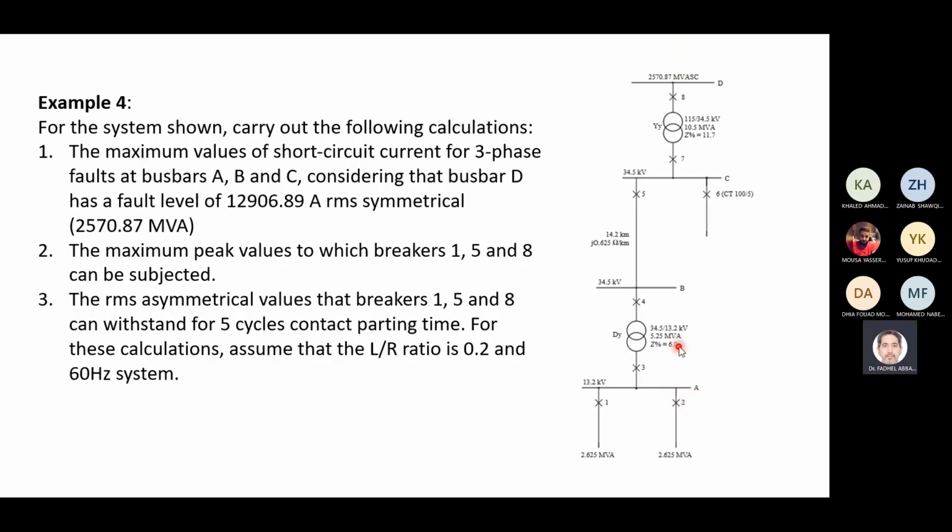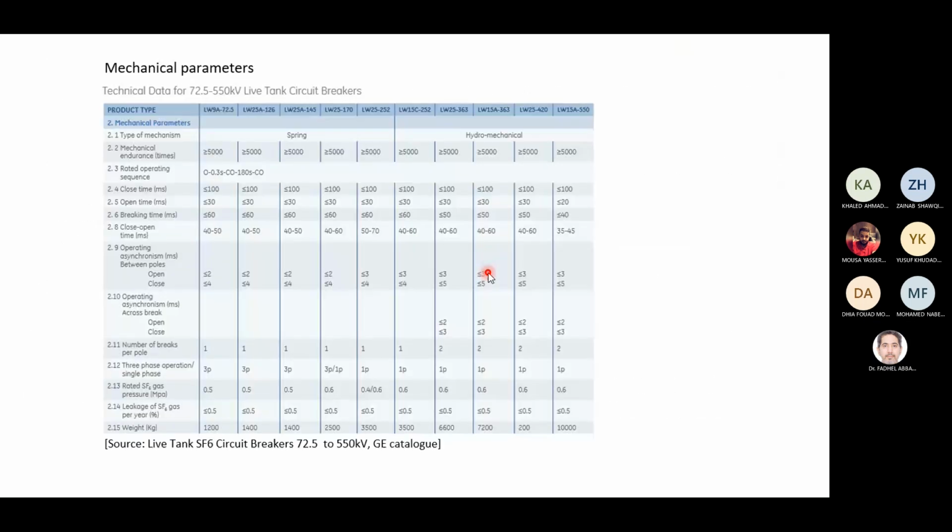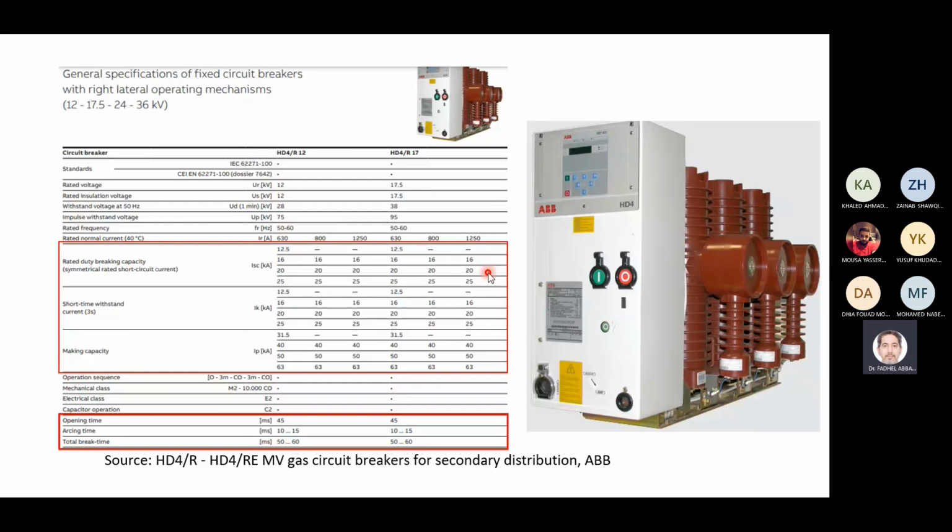أوكي شباب. فإحنا علشان نتجنب إننا نروح على الكومبلكسيتي، وش يسوون عادة في السيركت بريكر ريتنج؟ أنا الحين بختار سيركت بريكر هني وأعرف الشورت سيركت ليفل هني، أروح مجرد آخذ 25% higher than this short circuit، وما أحتاج أحسب الإكس آر ريشيو، أضيف بس 25% higher than short circuit level.